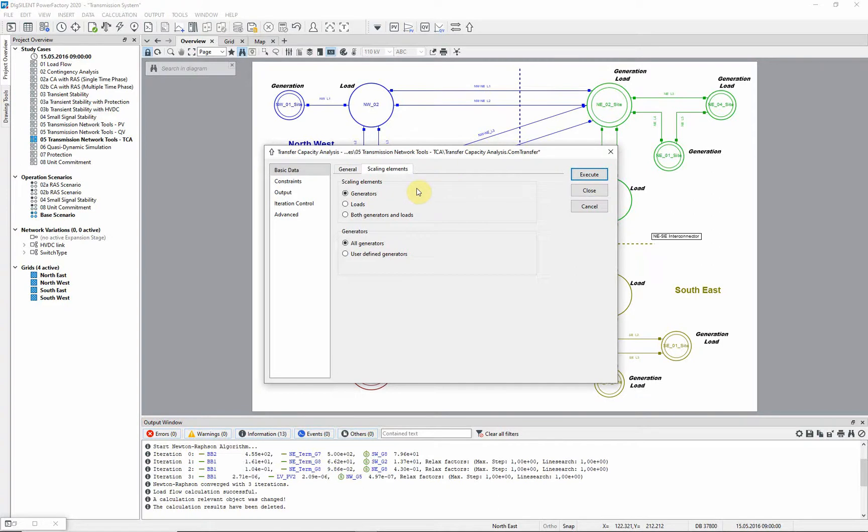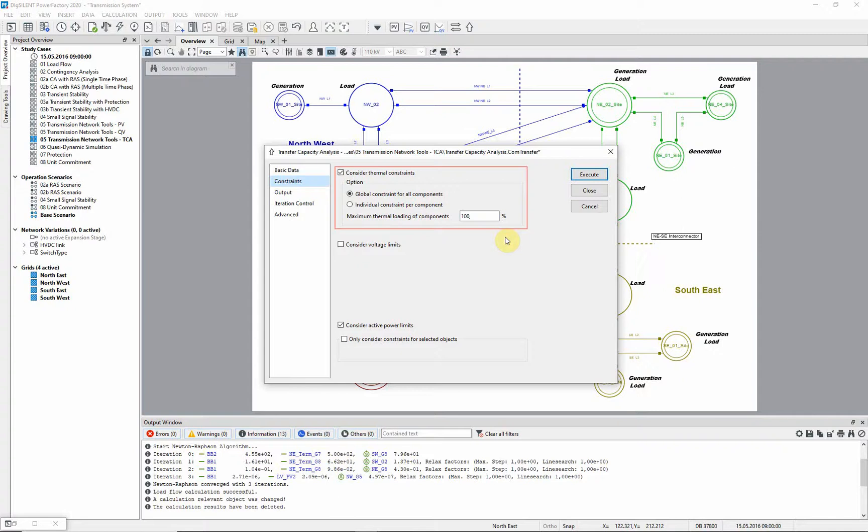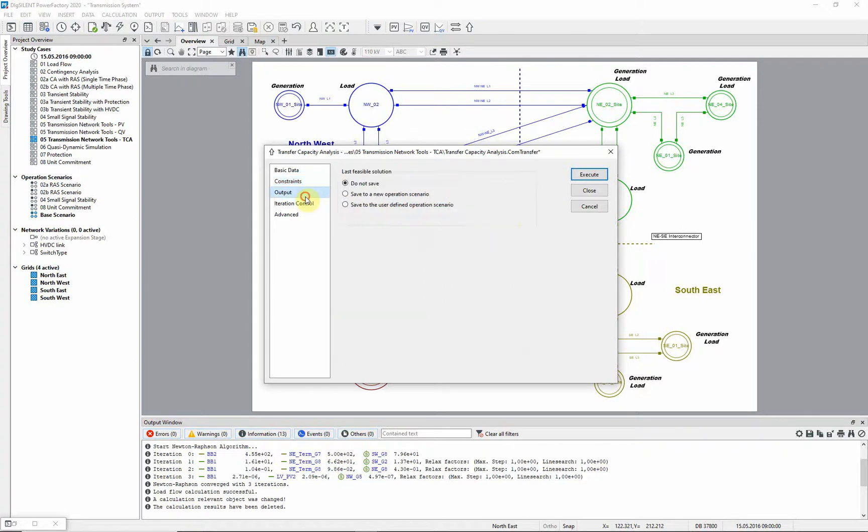We now look at the constraints page, where the constraining limits are defined. The option to consider thermal constraints is selected, meaning that the thermal ratings of branches will act as limiting factors. In addition, the active power limits of generators will be observed. There are also options to save the output of the analysis but in this example we will not do this.